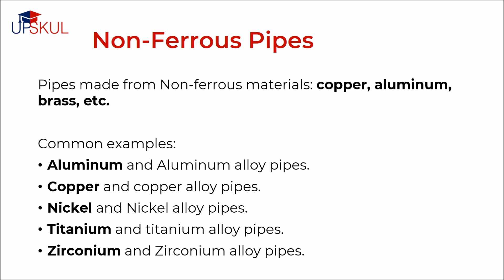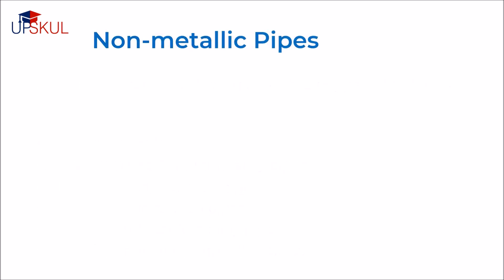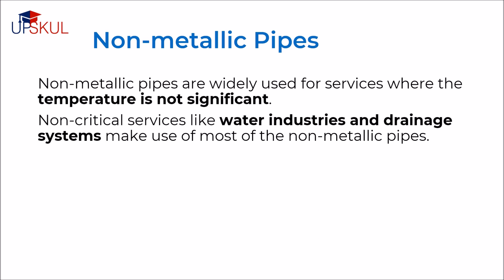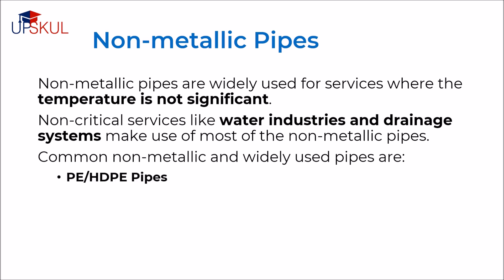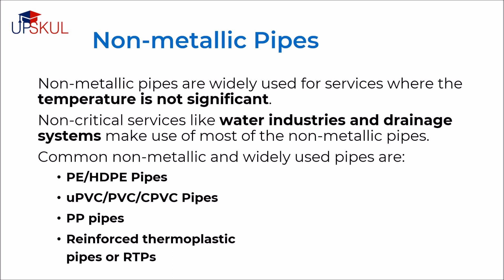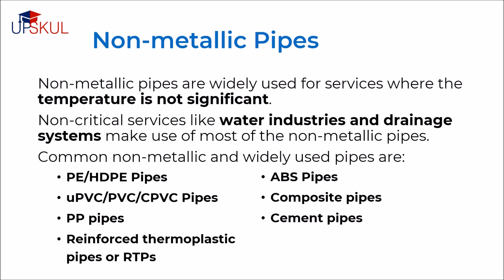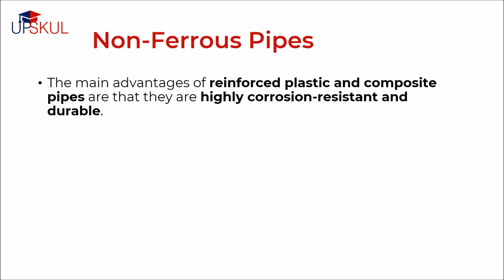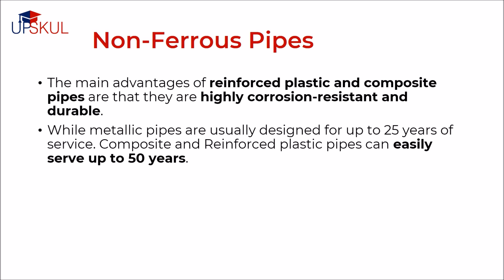Non-metallic pipes are widely used for services where temperature is not significant. Non-critical services like water industries and drainage systems make use of non-metallic pipes. Common non-metallic pipes could be PE or HDPE pipes, UPVC, PVC and CPVC pipes, polypropylene pipes, reinforced thermoplastic pipes or RTPs, ABS pipes, composite pipes like GRE, GRP, FRP pipes, cement and asbestos pipes, and vitrified clay pipes. The main advantages of reinforced plastic and composite pipes are that they are highly corrosion resistant and durable. While metallic pipes are usually designed for up to 25 years of service, composite and reinforced plastic pipes can easily serve up to 50 years.